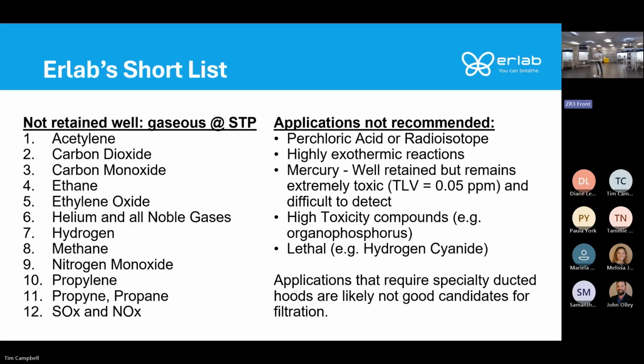They typically would need a specialty ducted fume hood. So for perchloric acid, you need a washdown hood. For radioisotopes, you need a specialty line hood. Anything that's highly exothermic, open flames, you're going to want a canopy hood to dissipate the heat. Now there are chemicals we can retain, such as mercury, but we don't recommend using it in our hood because it's extremely toxic, has a very low threshold limit value, and it's difficult to detect breakthrough. That's the same with anything that's immediately lethal, like hydrogen cyanide. We know we can retain it. We've actually tested it, but we don't recommend its use in the hood.